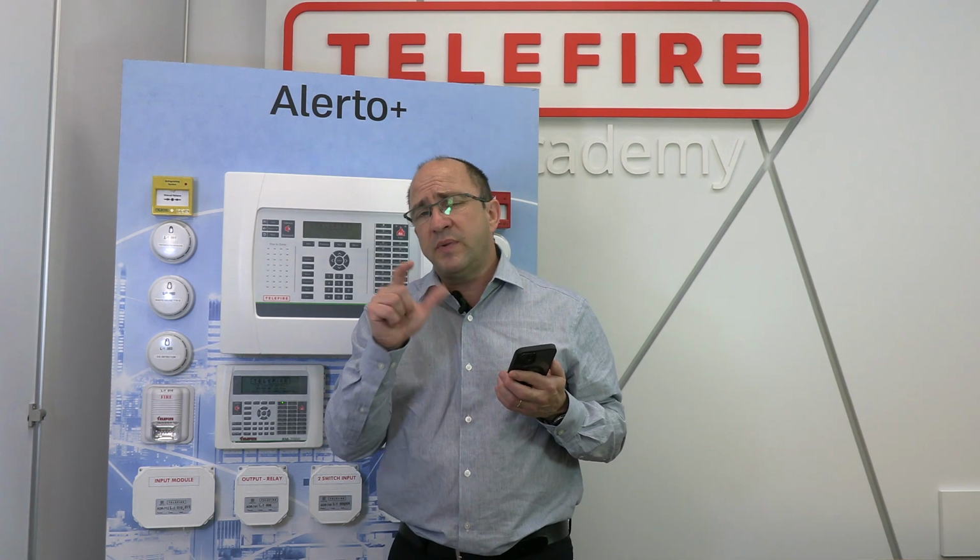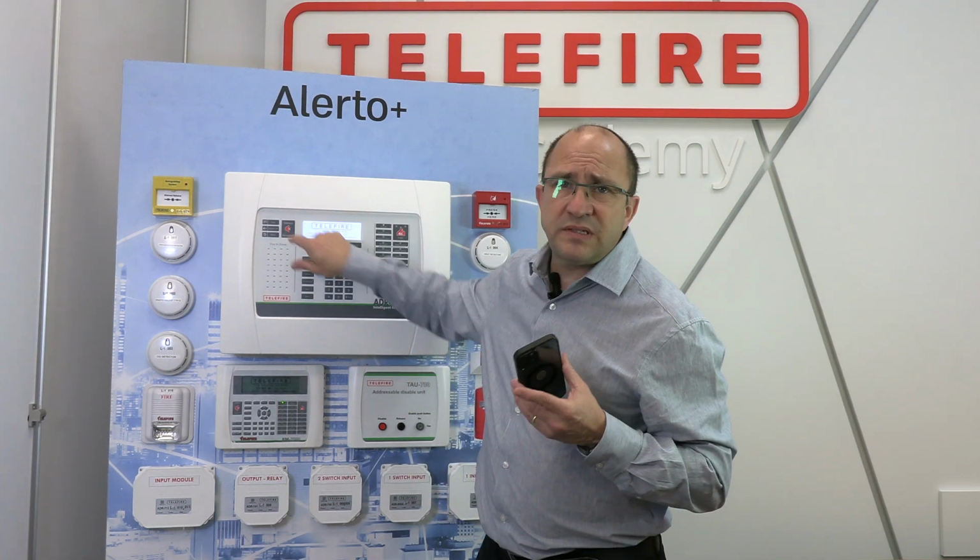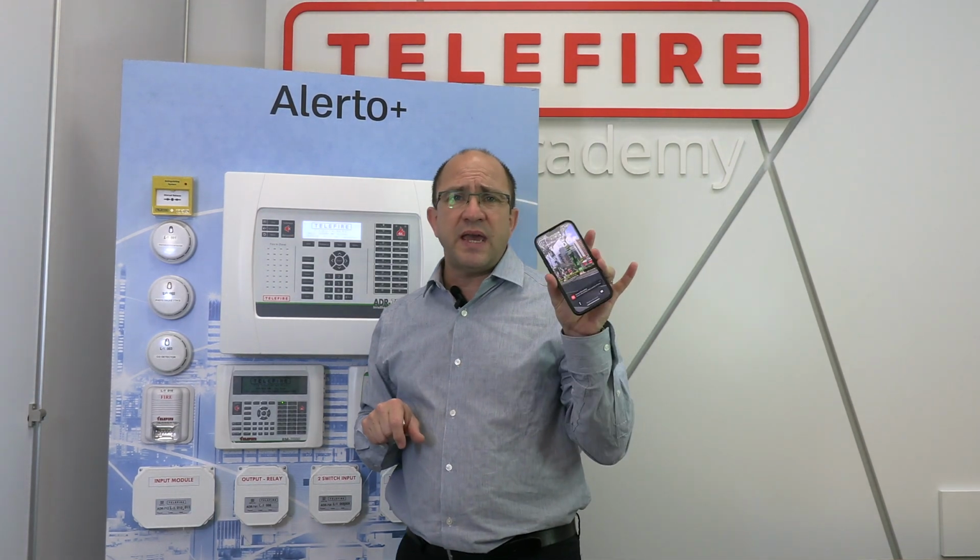silence for the buzzer, silence for the whole system. By the way, if you do silence for the whole system, since we would like you to walk around and see why the siren was activated, only after 1.5 or a bit more minutes, only then it will be silenced through the application. If you would like to silence it straight away, you go to the control panel and press silence. But through the application, at least 1.5 minutes before it's silenced.